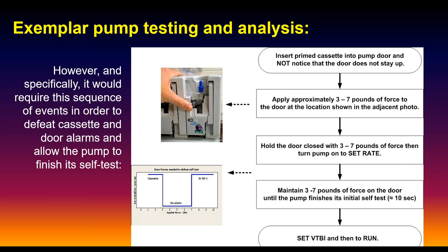Because the pump was working fine in the OR. Patient came up from the OR to the PICU, same pump. So someone in the OR would have had to have done that if it was broke. Someone in the PICU would have done that. And of course, ultimately what I concluded is that there's nothing wrong with the pump, but in the process of switching the epi out to the packed red cells, that valve got moved. And unfortunately, and this is kind of nursing 101, the IV line wasn't clamped off before it was removed. And that's what ultimately caused it.